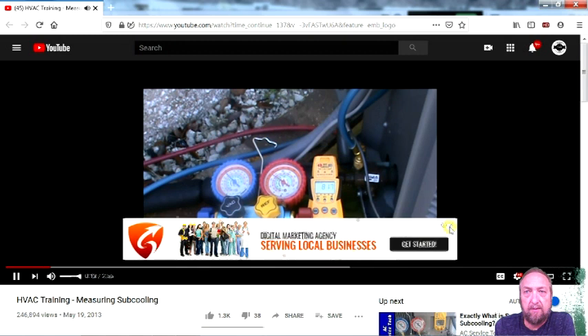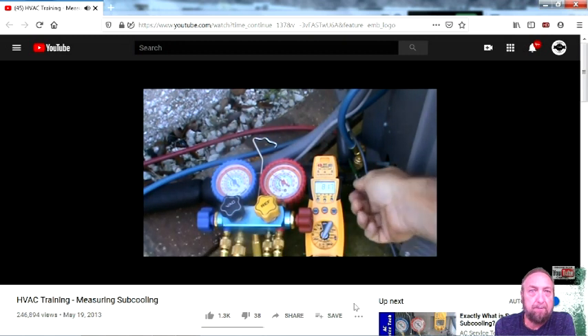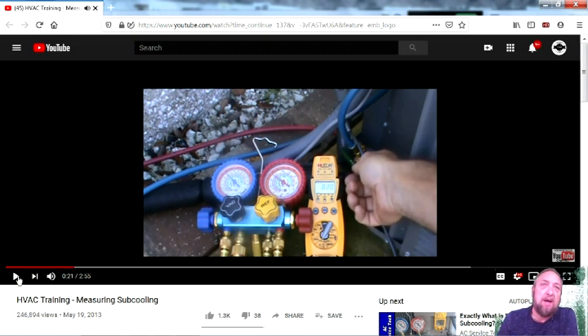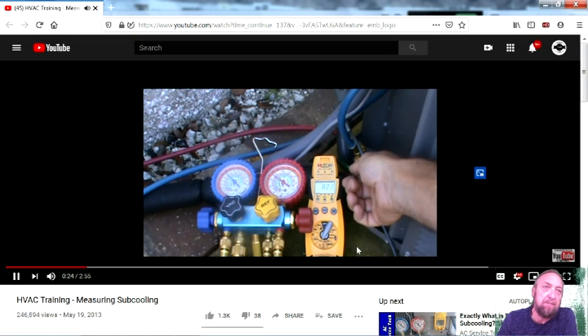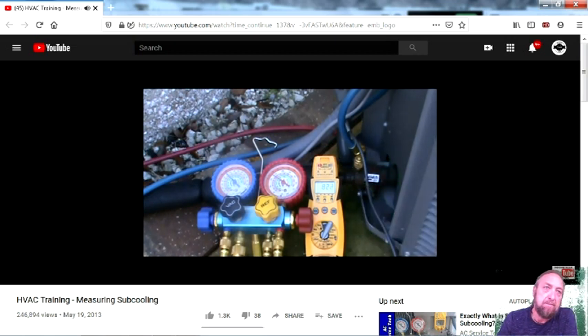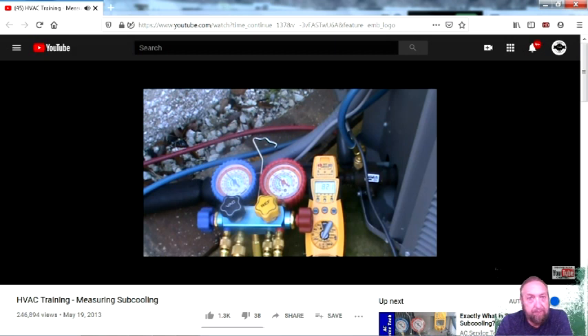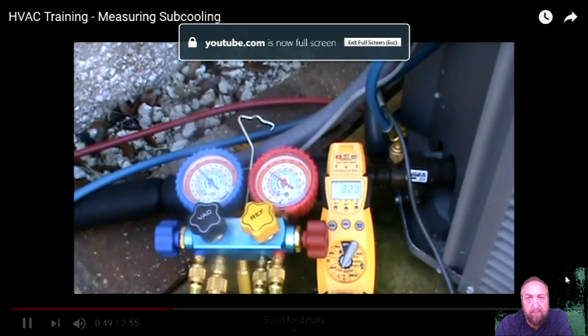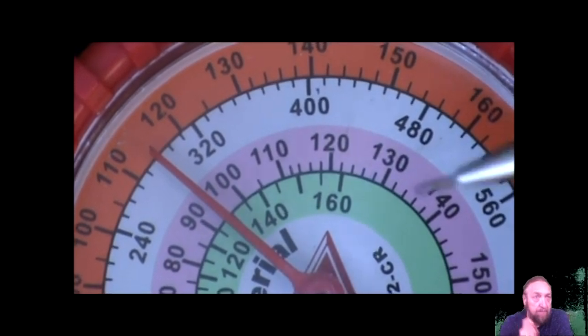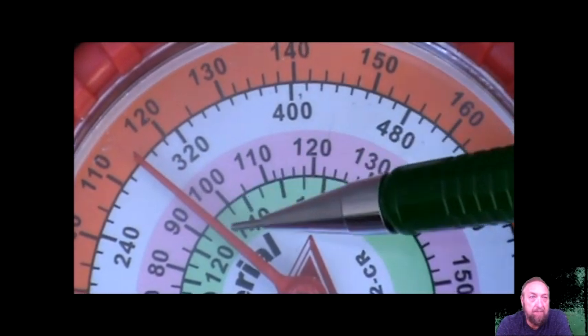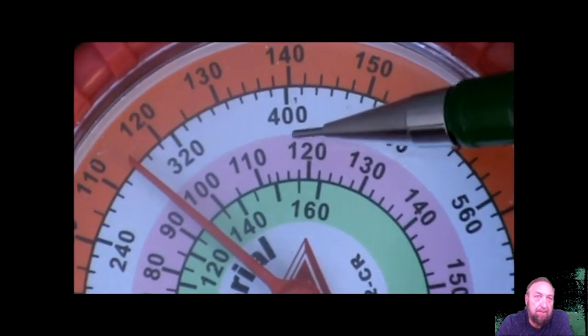Measuring subcooling: the gauges are hooked up and the temperature probe is clamped onto the high side liquid line. You can't really see it, but it's behind the suction line where the blue hose is connected. The red hose is connected to the liquid line measuring the temperature of the refrigeration piping as it leaves the condenser. We don't use our gauges so much to measure pressure as to determine what the saturation temperature of the refrigerant is.